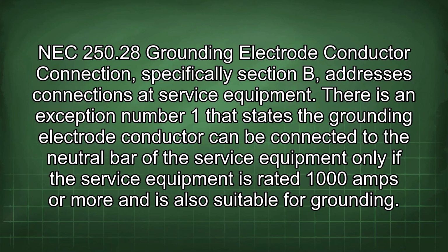NEC 250.28 grounding electrode conductor connection, specifically Section B, addresses connections at service equipment. There is an exception number 1 that states the grounding electrode conductor can be connected to the neutral bar of the service equipment only if the service equipment is rated 1000 amps or more and is also suitable for grounding.